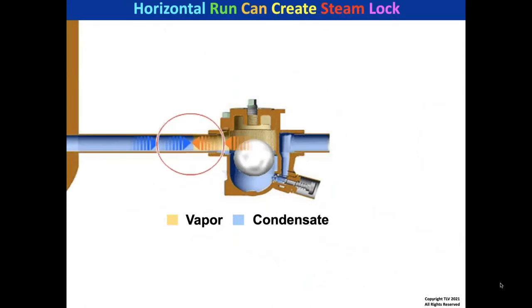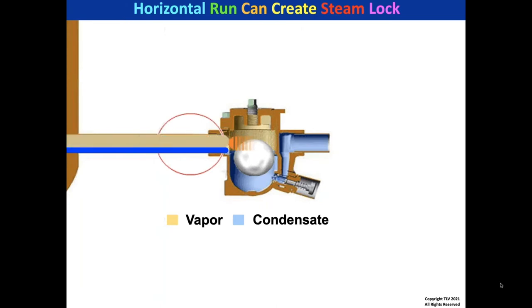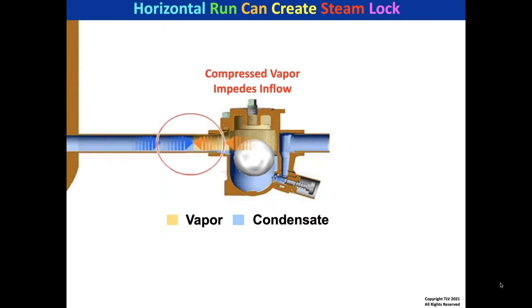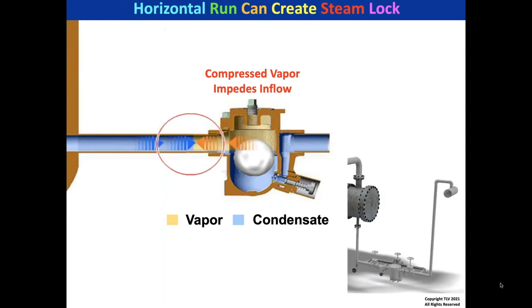Most people don't realize that if a trap is on a long horizontal line, condensate is so small by volume that it runs across the bottom of the pipe while vapor runs across the top. The trap sees vapor — it sees steam — and it locks. It thinks it's supposed to stop steam from leaking. This compressed vapor impedes flow, known as a steam lock or vapor lock. The simple mitigation is to install a drop-down to the trap, not have a long horizontal run after the drop-down.